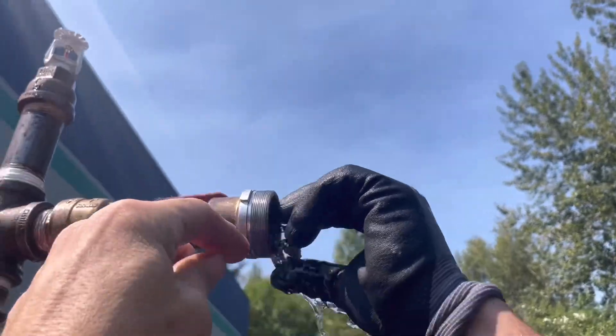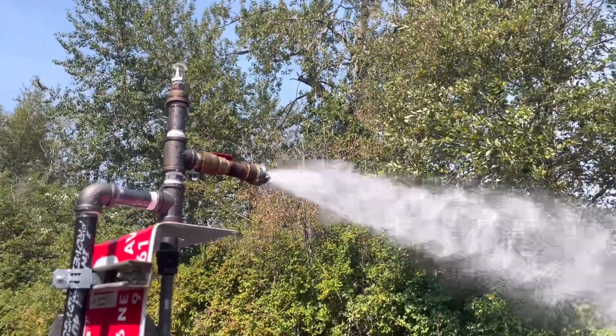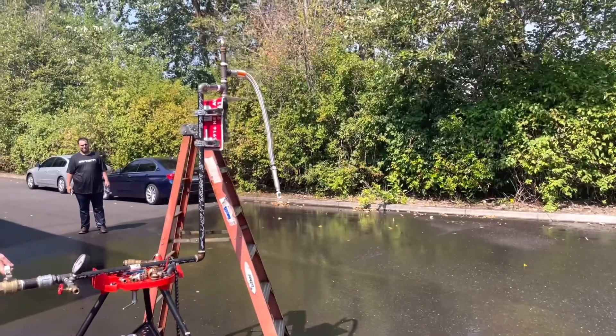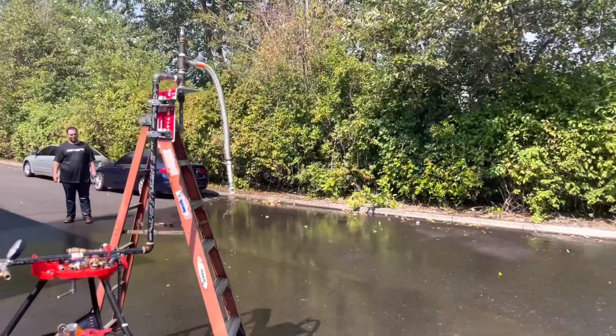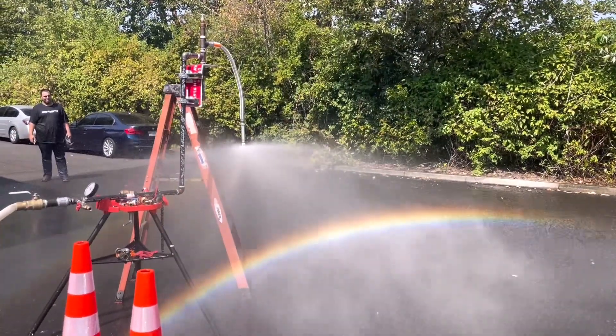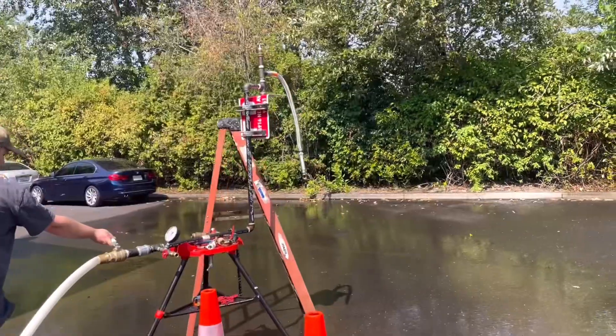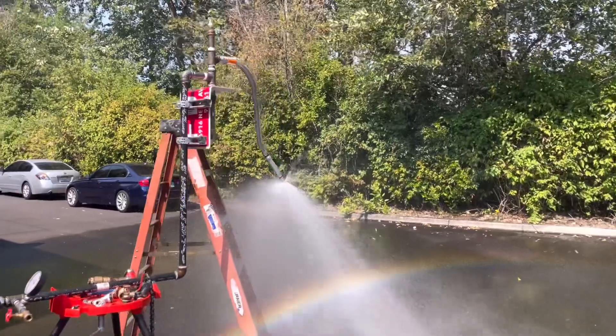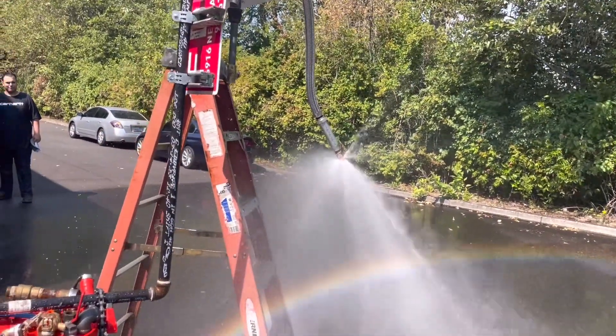What if you put one of these old-style concealers in the wrong way? Go ahead and start it — they don't work right. What if you had a whip that was unsecured? We have the glass bulb removed from it. Surprisingly, it didn't move around much. Horizontal sidewall — there's a little bit of thrust on that. Go ahead and shut it off.